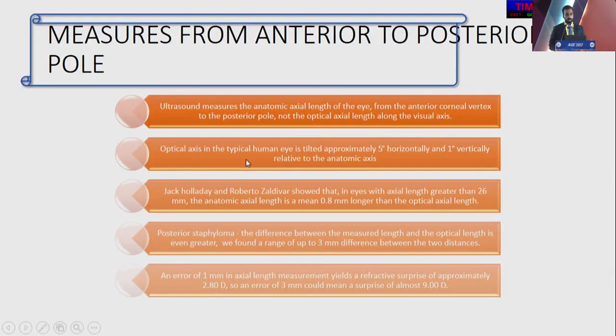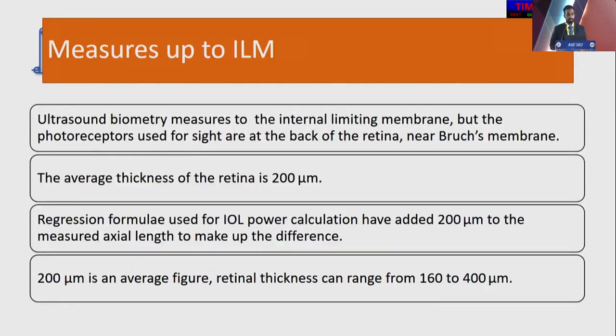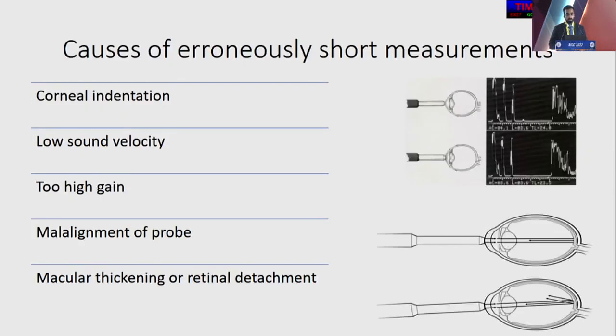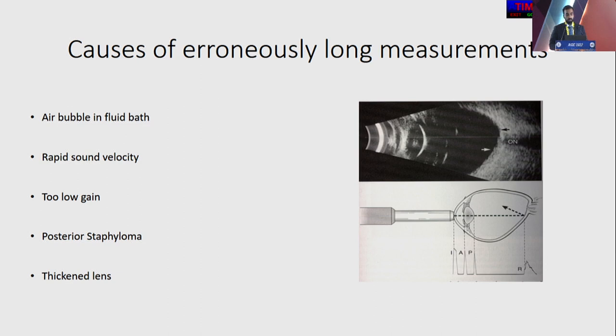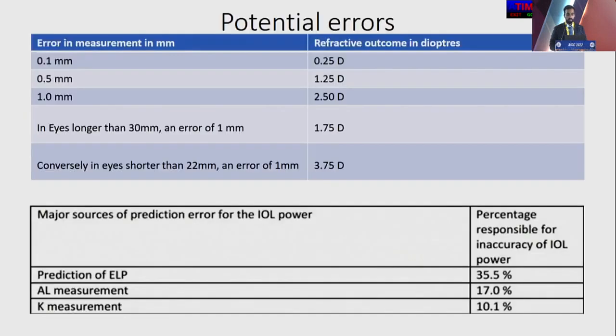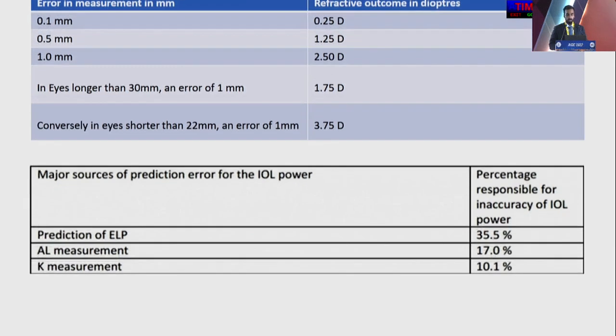So the drawbacks are it measures from the anterior to the posterior pole, so it only measures the anatomic axial length and not the optical or visual axial length. It also only measures up to the internal limiting membrane. It does miss out 200 microns of the retinal thickness, so you can have an error here. So the causes of an erroneously short measurement can be corneal indentation, low sound velocity, too high a gain, or a malalignment of the probe. And an erroneously long measurement can happen when there's a rapid sound velocity, too low a gain, or a posterior staphyloma. So the potential for error is more in a shorter eye, but it is more forgiving in a longer eye.